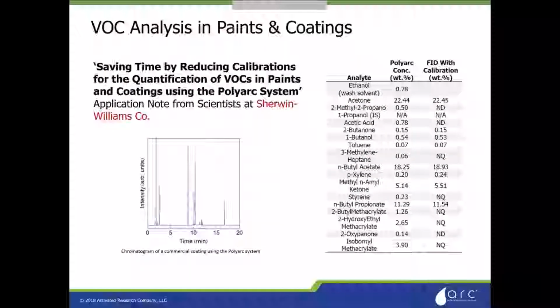So a large application that we see with the PolyArc, and also the topic of a recent ASTM method that was awarded with the PolyArc in it, is the VOC analysis in paints and coatings. So you've all probably seen low or no VOC paints, which are waterborne paints. And in order to get that low or no VOC rating, they need to be analyzed for 50 grams per liter or less VOC content, or 5 grams per liter or less for the no VOCs.